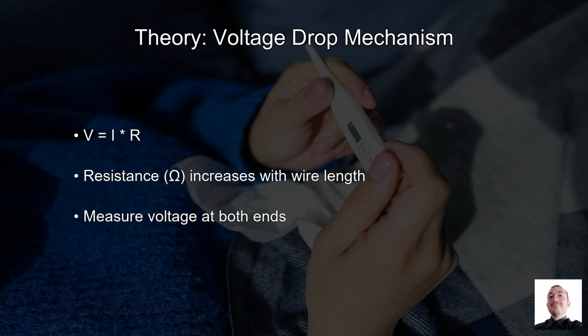The key parameter here is resistance, measured in ohms. The longer the wire, the higher the resistance, leading to a greater voltage drop. To calculate this, use Ohm's law, V equals IR, where V is voltage, I is current, and R is resistance. If you're experiencing issues with your equipment, like the welder in our example, a voltage drop could be the culprit. Measure the voltage at both ends of the circuit to confirm.